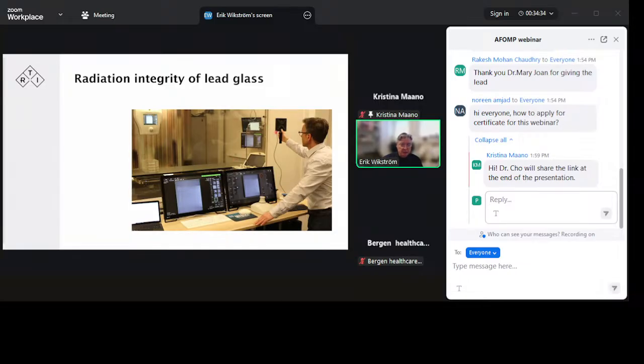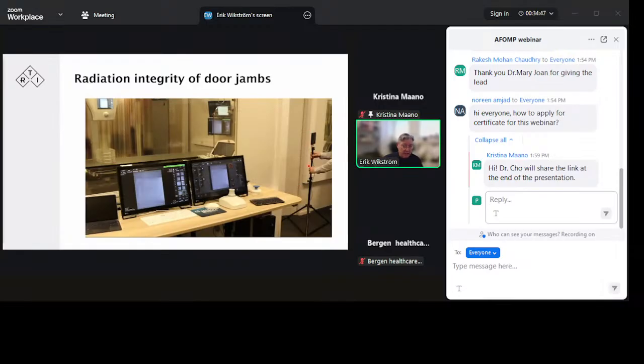So during the exposure, we can have the scatter probe on the inside to see what kind of radiation penetrates the lead glass. Could be checking the door jambs as well. Here's a door. It might be a little bit tricky to see, but a door into the room, so you can place the probe, the scatter probe, right there. Here's a tube. Scatter is generated from the slabs and then shoots out in different directions, so we can see how efficient the radiation trap in the door jamb is.